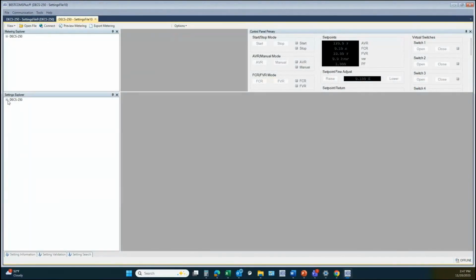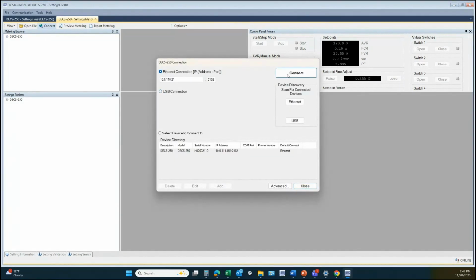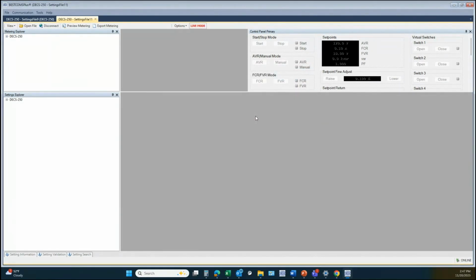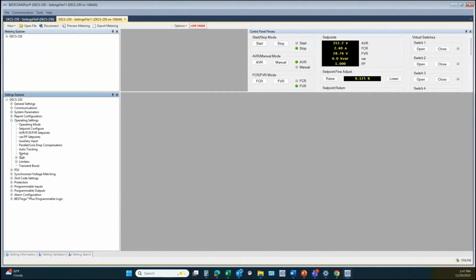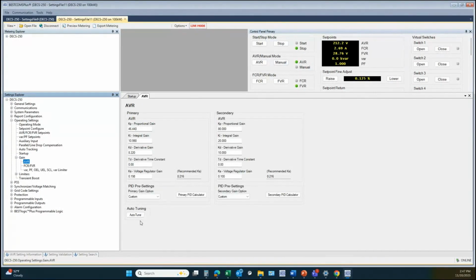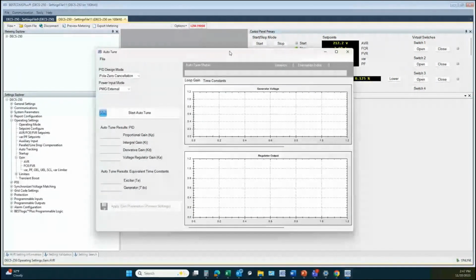I am going to connect to a different DECS real quick, just so I can show you what that auto tuning looks like. When you perform the auto tuning, you need to be offline. You cannot have your generator actually supporting load or tied to any other source of power. So the generator breaker needs to be open, and the DECS needs to know that. And then you have pole zero cancellation or pole placement as options. And then PMG or external for your power source, or shunt powered.